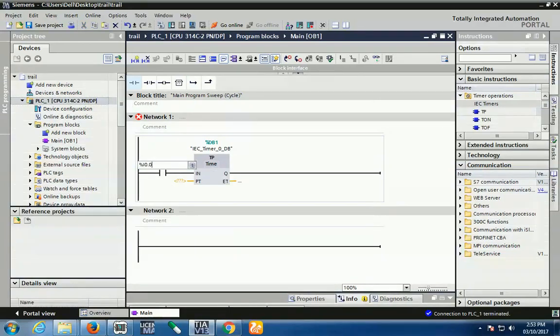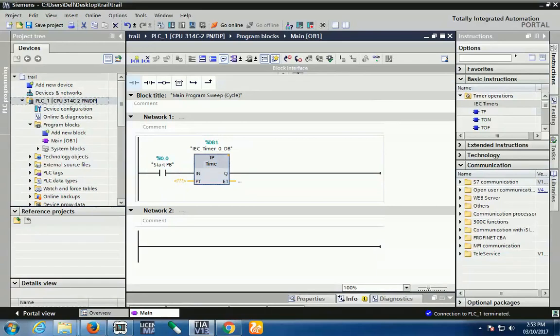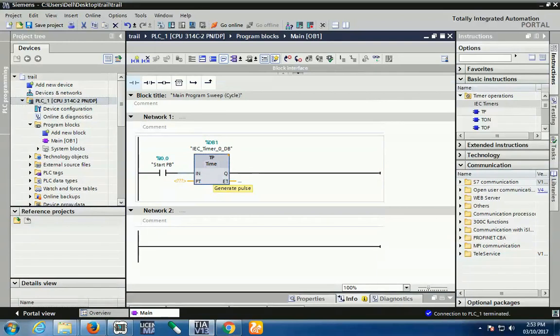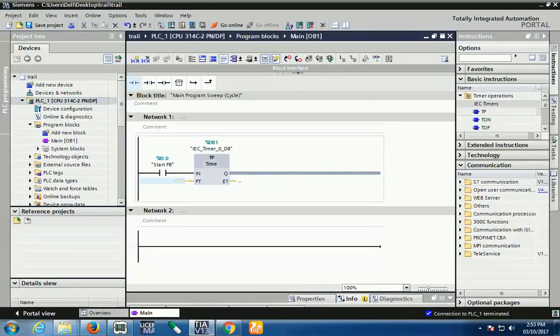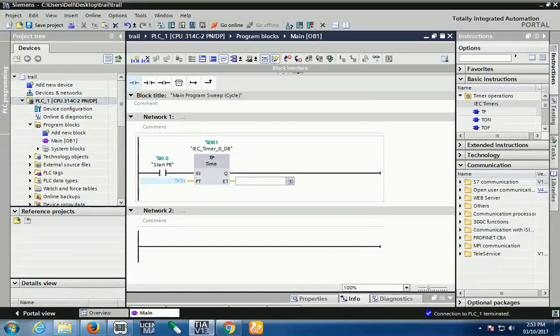Here I configure input I0.0. When I press the input, your pulse timer is working on the positive edge, meaning by default the signal is 0, and when I press the input, the signal becomes 1 and your timer is activated. In pulse timer, if your timer is activated, your output should be on, but for how much time? That time is mentioned in preset time. Suppose I want 5 seconds, I just set 5 seconds.